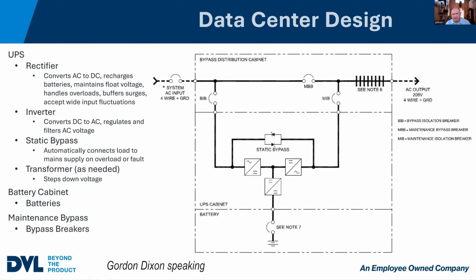And you know what, let me go ahead and just touch on that now. A flywheel is, instead of having batteries, right? If a UPS has battery cabinets, it's going to be a cabinet filled with 40 batteries that look like car batteries. And you might have 4, 5, even 6 more of those. Sometimes instead of using DC power from a battery, they use flywheel, and that is basically using stored kinetic energy. So what's happening is it's essentially a large cylinder with a flywheel attached.